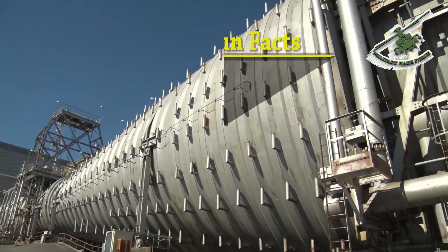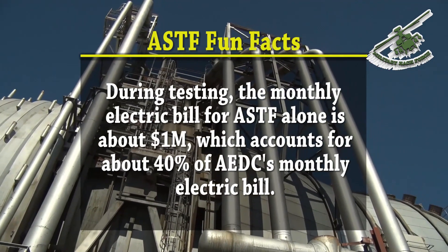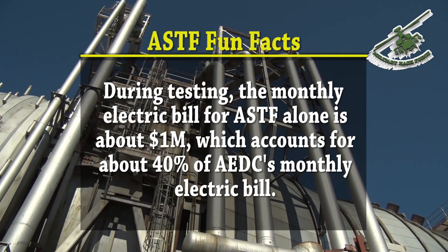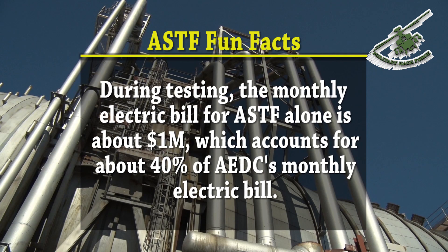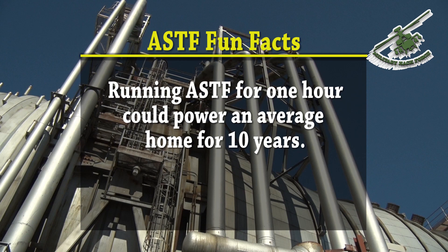Cooling towers are used to cool the 300-degree water down to about 70 degrees before recirculating it through the system. During testing, the monthly electric bill for ASTF alone is about $1 million, which accounts for about 40 percent of AEDC's monthly electric bill. Running ASTF for one hour could power an average home for 10 years.